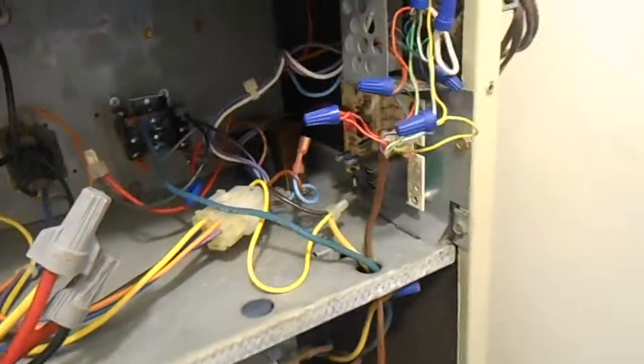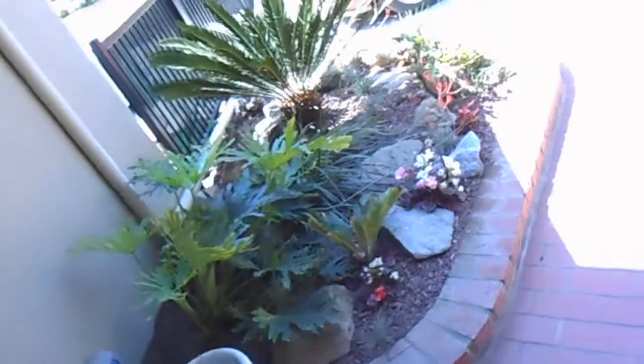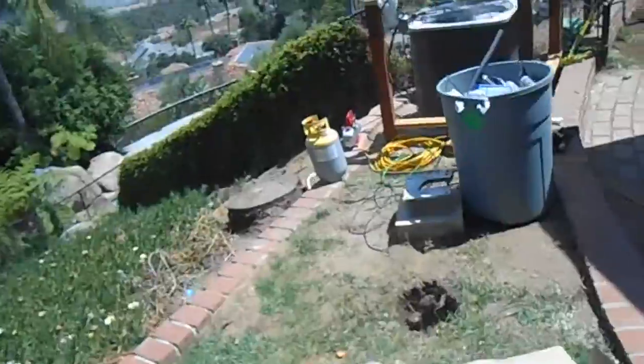All right. We're back at this job. We didn't have enough time to get a blower board. We need to get it working, so I just got a little pin relay to get the fan to work. This panel back on, and this thing is just a veritable potpourri of electrical issues. And so we're charging the refrigerant back in.